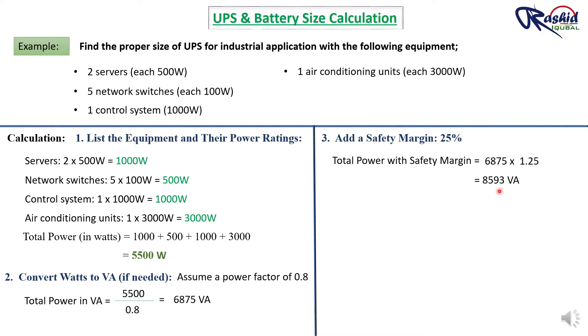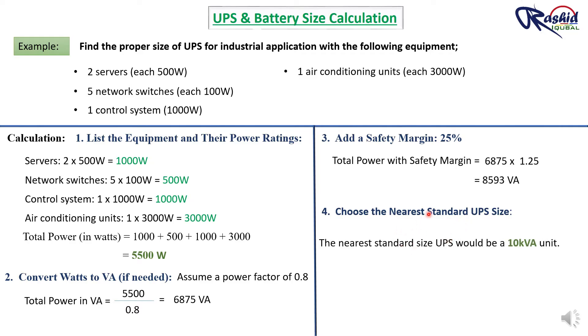This is the total consumption of our system. Since an 8593 VA UPS is not available in the market, we go with the nearest standard size available, which is 10 KVA. This size of UPS is perfect for the given load.